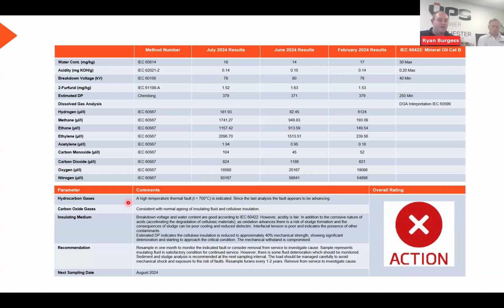And looking at the furans, they're just under that 400 mark we spoke about. So once you're there, if they had just decided, oh, we're going to degas it rather than do some work, lost that furan data, and potentially some reclamation work can actually do more harm than good, especially when the furan has been degraded to a certain point. So again, if we put new oil in, or we do some reclamation work, it can cause more harm than good. And that was indicated through this particular report, that it was an active fault and that they needed to take action. It wasn't just a one-off.